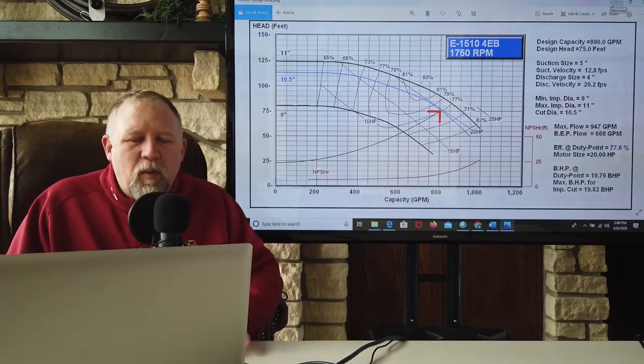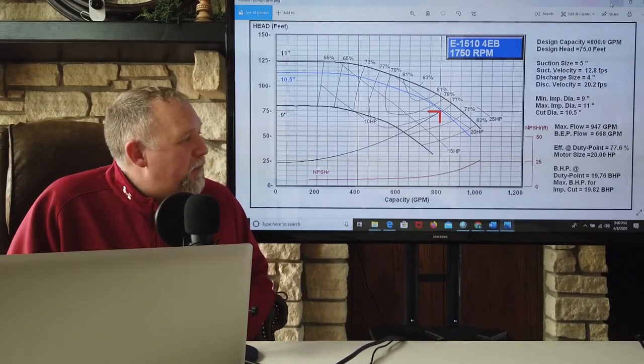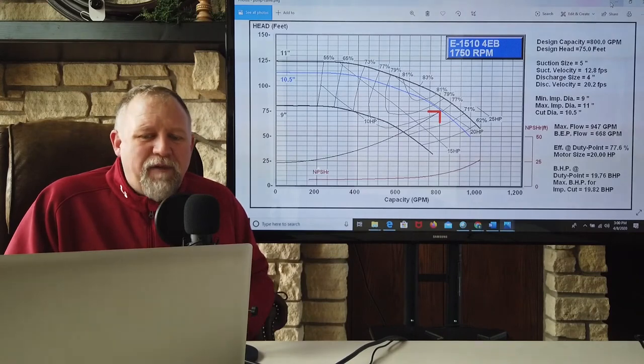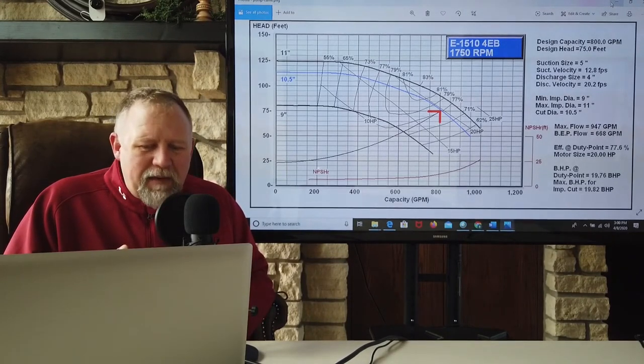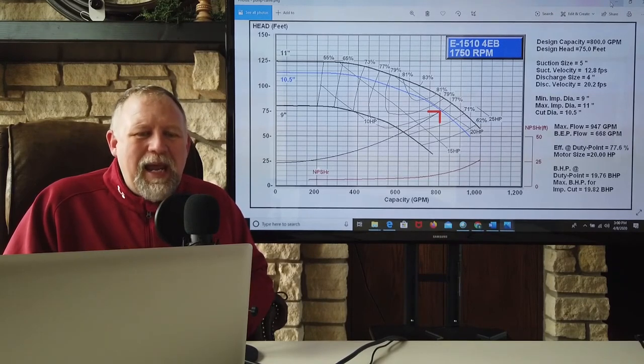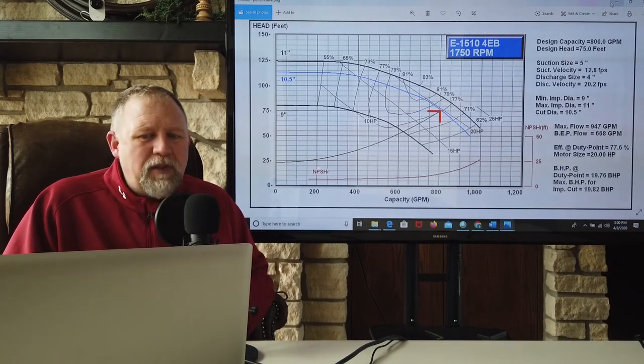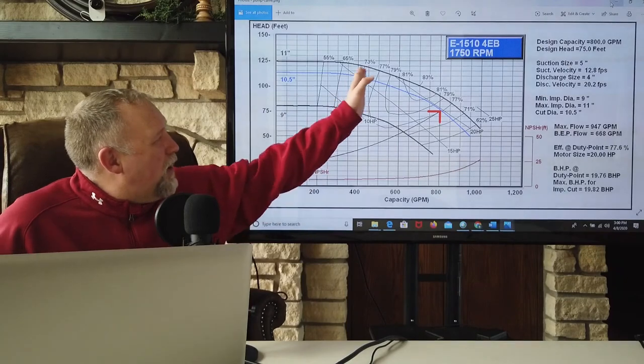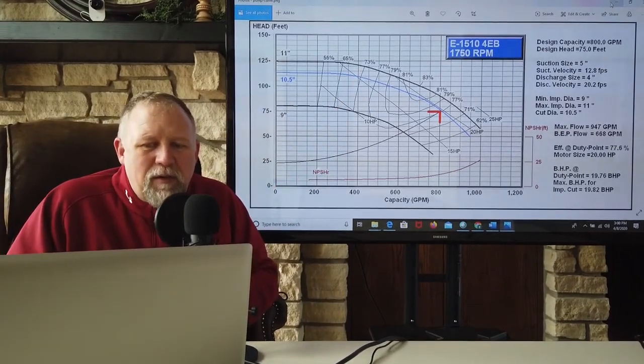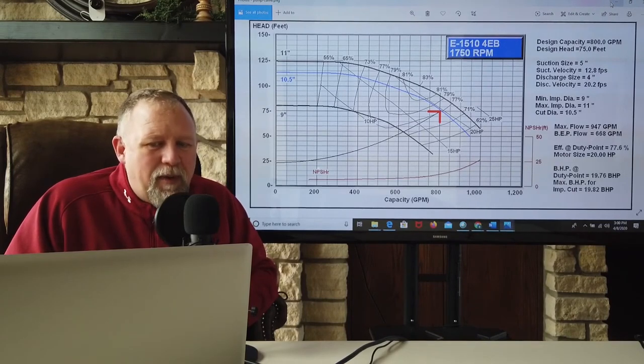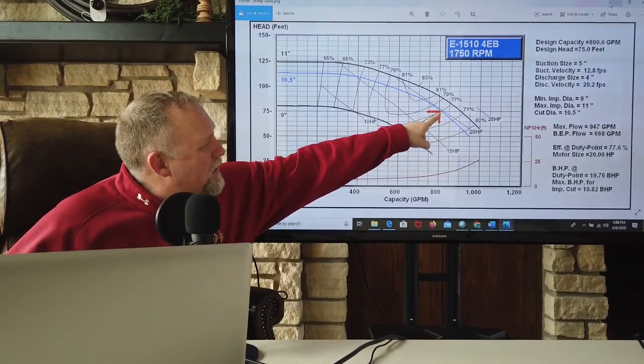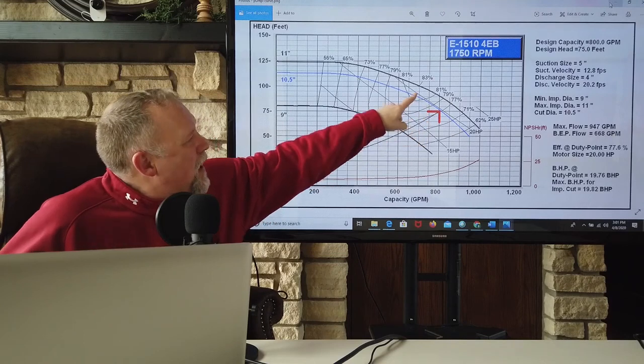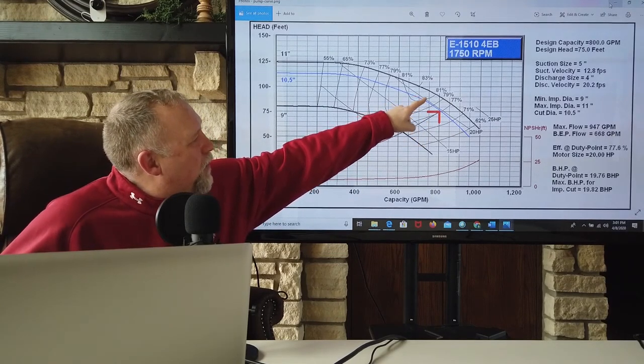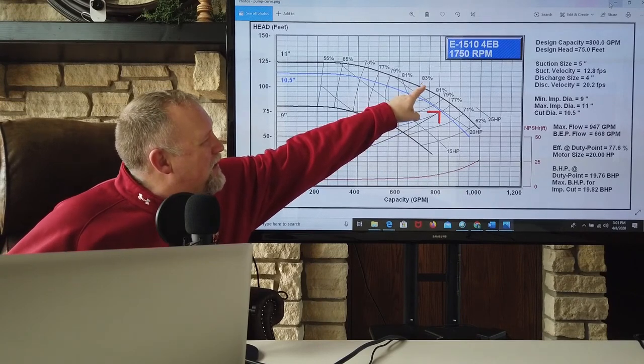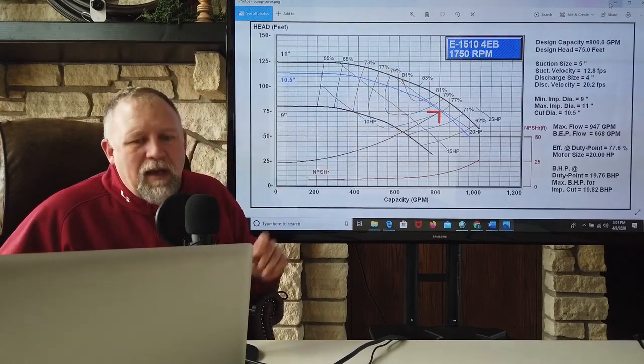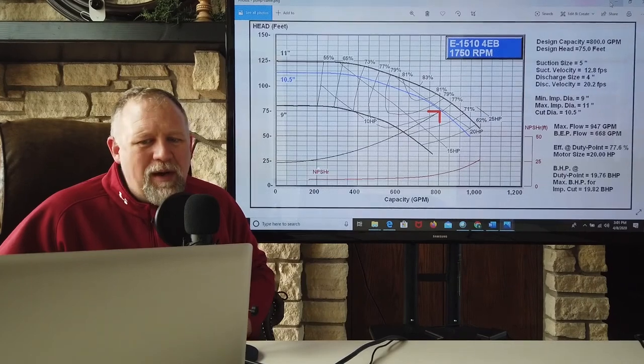All right. So, with that in mind, some takeaways that you need to get from this. If I give you, say on an exam someday, a combination of flow rate and pump head, I would expect you to be able to look at a chart like this and pick which impeller you would have to use. I would also expect you to be able to tell me about what efficiency it is operating at. In other words, wherever that point is, we could say, all right, I'm operating at 77% efficiency. Maybe I was right here. We could say, all right, 81% efficiency is here, 83 is here. Maybe that's like 81.5 or something. I want you to be able to look up the efficiency and figure out about where it's at.